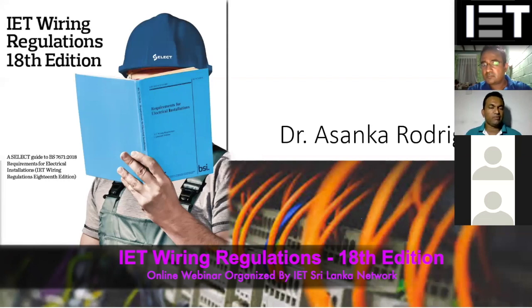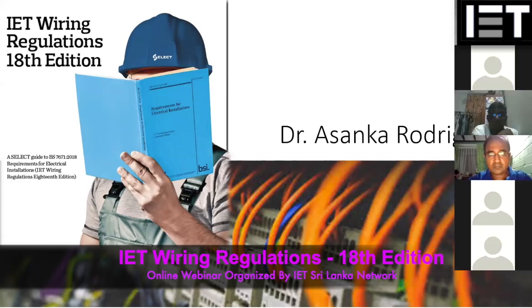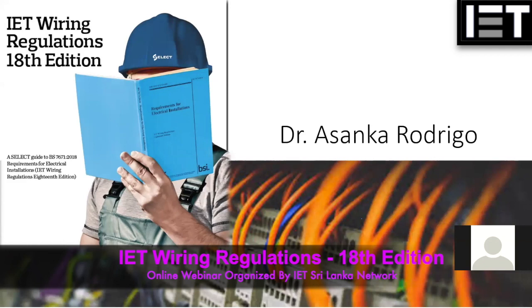But in most of the other types, when you look at the driver circuit itself, almost all have an earth connection. If you look carefully, most of the driver circuits come with the earth connection. That is also needed for harmonic filtering, because there is the EMC filter, and for that EMC filter to work there should be an earth connection as well. So the earth connection is provided for the driver circuit. And if the LED has exposed conductive parts, then they should be connected to the common earthing. Generally the reputed brands come with the earthing connection.